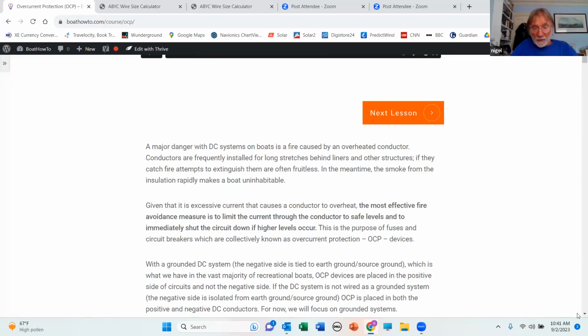The corollary to that is that the fuse or circuit breaker has to be at the front end of the circuit. It has to be close to the source of power, which in our case is the battery, because the battery is the piece of kit that has the ability to create a huge number of amps down that conductor. So the fuse or circuit breaker has to be at the battery end of the circuit.